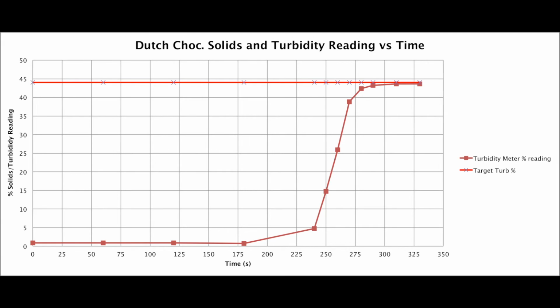I determined through time study experimentation that the 330 seconds was too long of a set point. The valve comes on at least a full 30 to 45 seconds after all the water has been purged and pure product is going straight into the drain. This time can vary with different products.